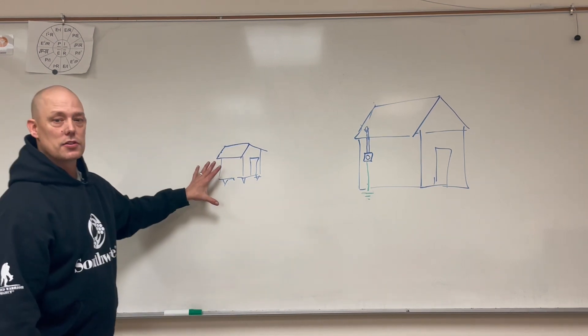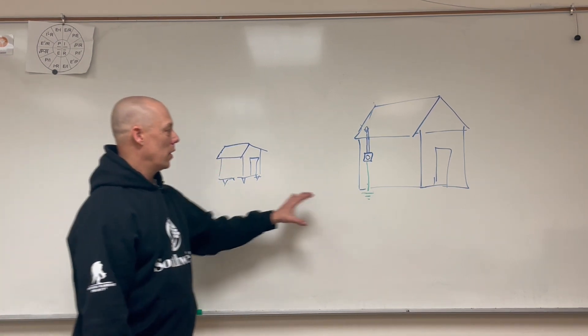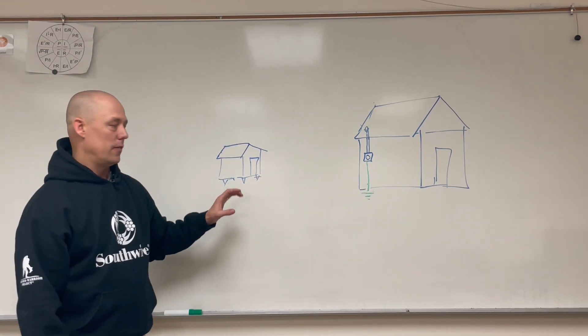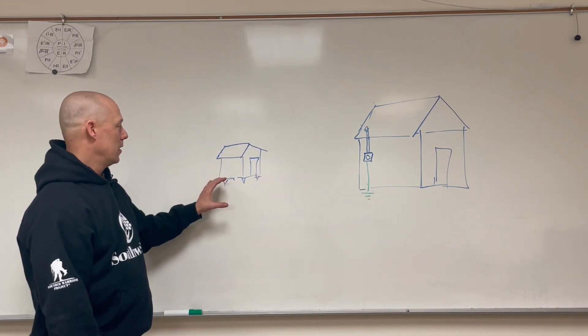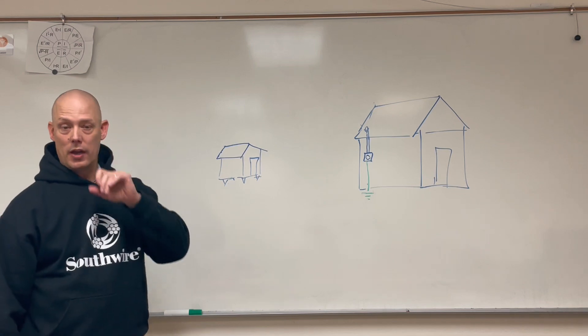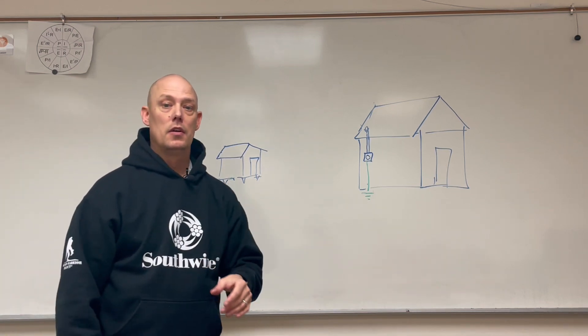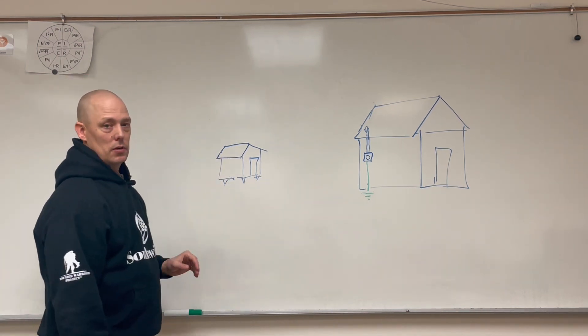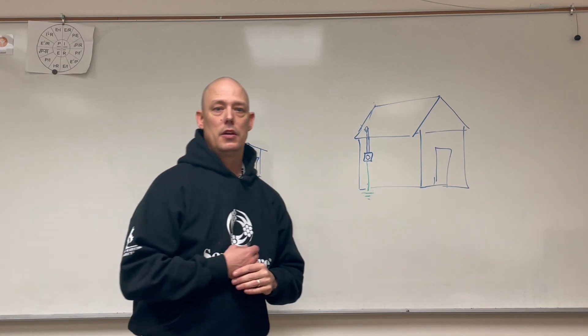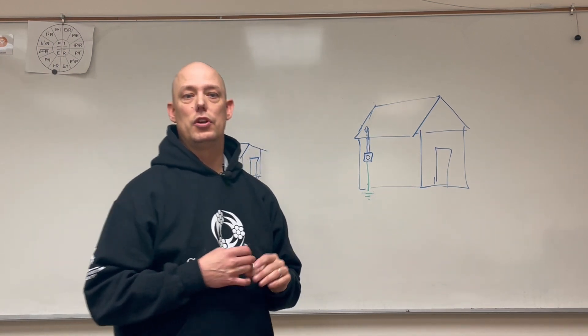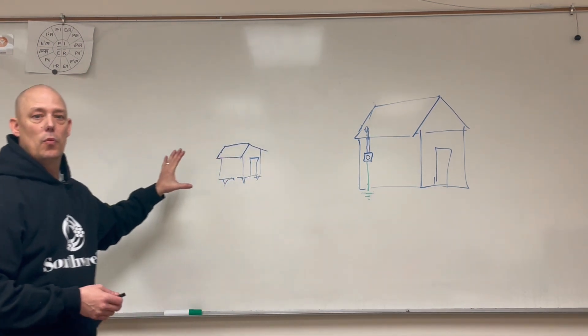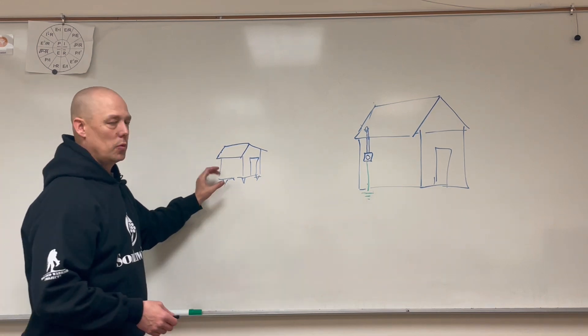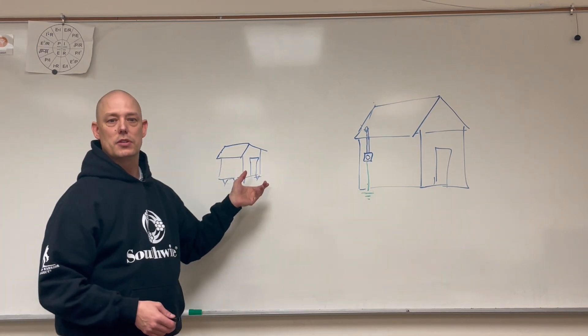Let's pretend this is a shed, and you want to take power from your house to that shed. If you want to have a receptacle at that shed with no light, that's okay. If you want to have a light with no receptacle, according to 210.52G2, whenever we have power at an accessory building, we have to have a receptacle.